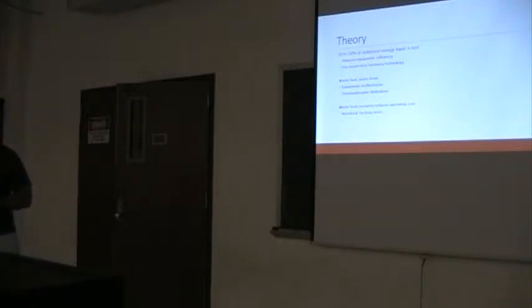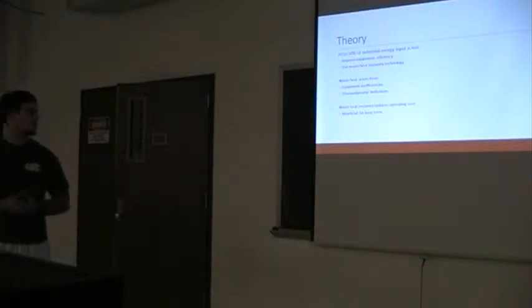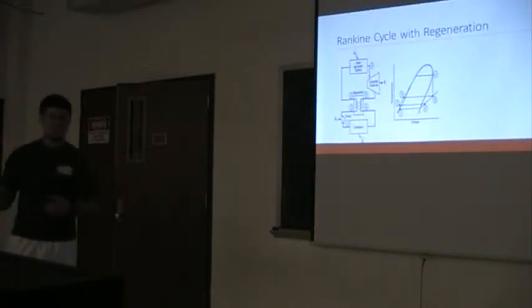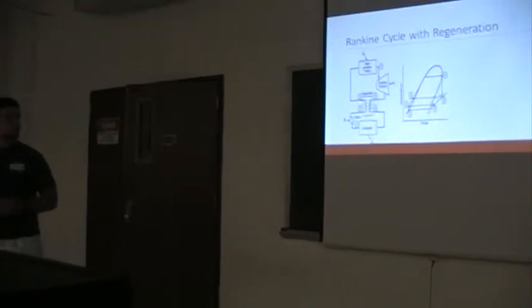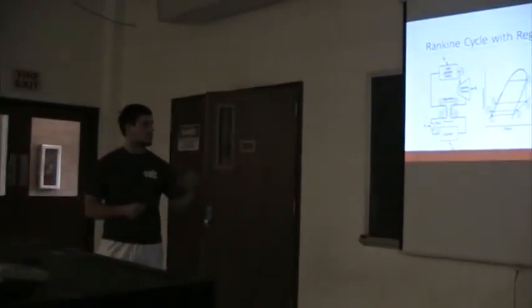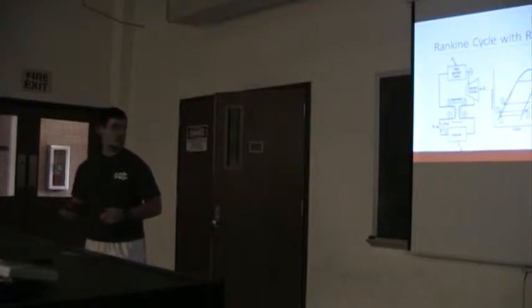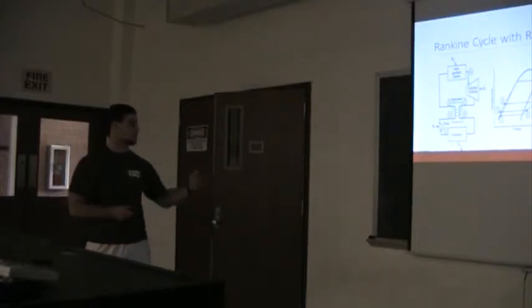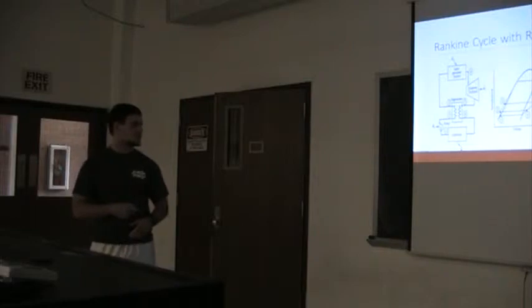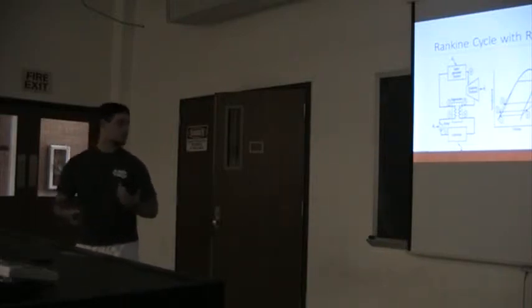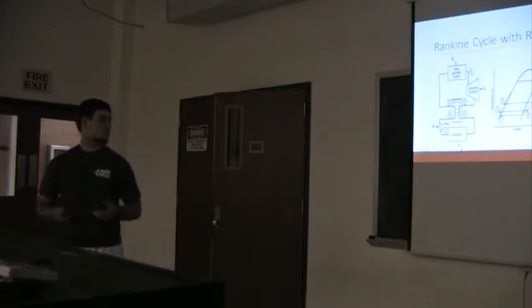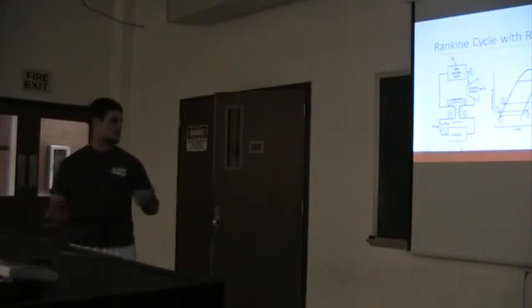Waste heat recovery reduces operating costs, beneficial for the long term. It might not be so beneficial for short term just because of the capital cost or the initial cost of the technology. Some of you might be familiar with the Rankine cycle with the regeneration. We see that the heat that comes out of the turbine is actually added to the liquid after the pump, which raises the temperature from point 2 to 3, which in the result the boiler has to put less heat into the fluid itself to go into the turbine.